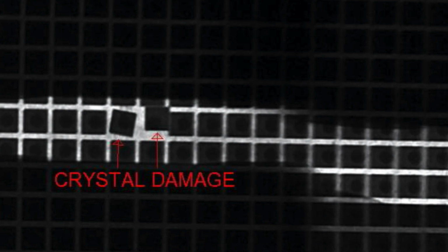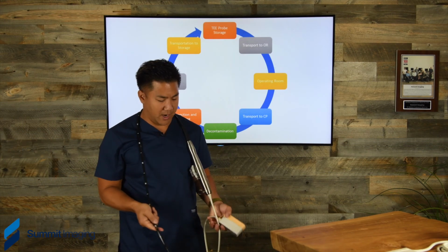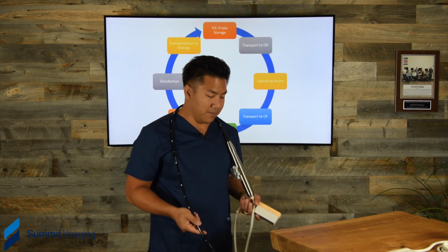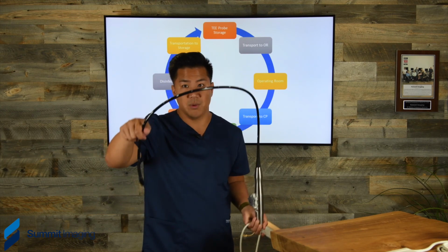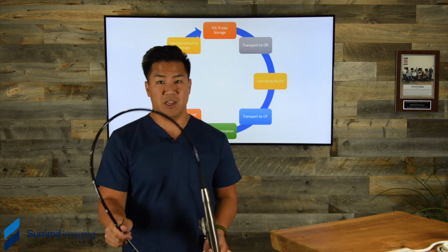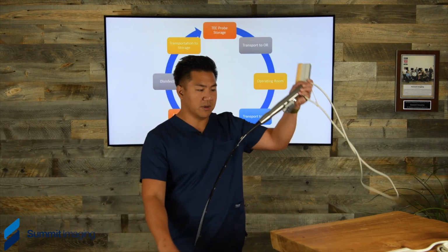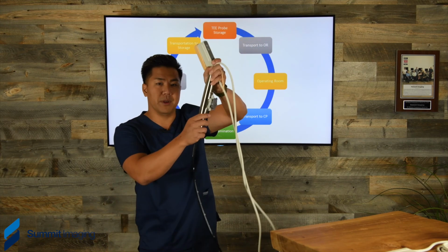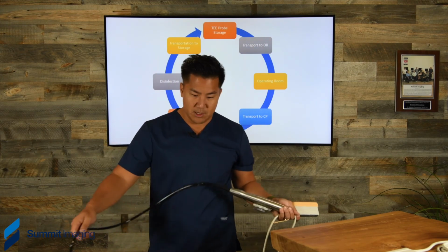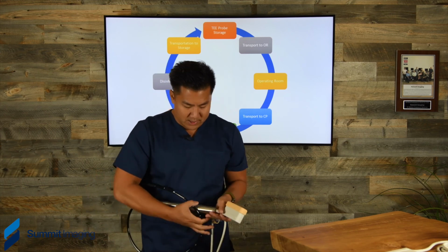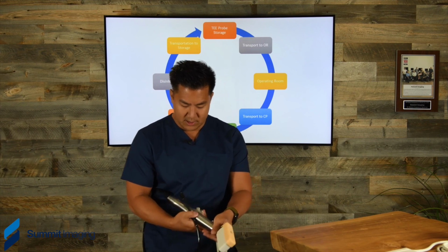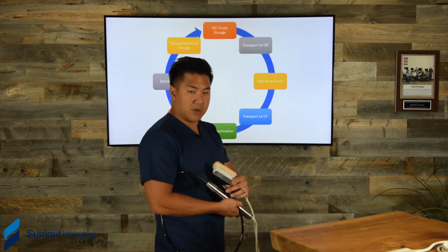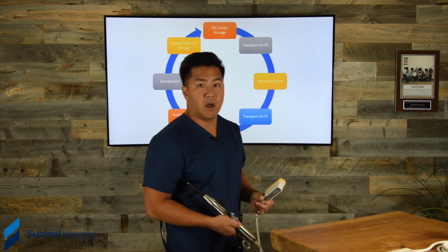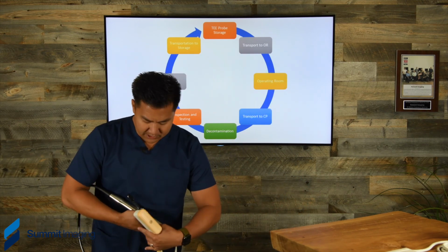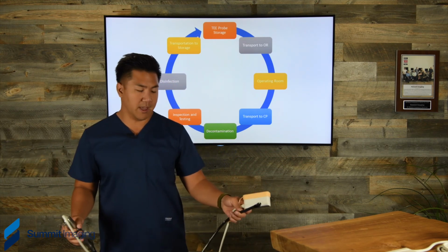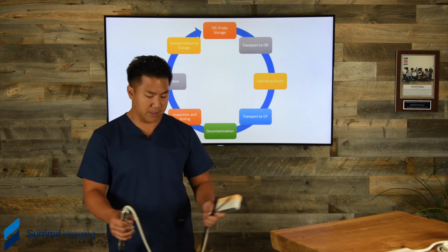And so what we've seen is everything from hospital employees trying to carry it like this, which we don't recommend, because you don't want this touching you, especially after it just came out of surgery, or if it just got used on a patient. You really don't want this entire insertion tube touching you at that point without the proper protective gear. We've seen people roll them up with the tip right here, and as they're walking around, the tip starts banging, as you can hear right now, on this metal casing here. We've even seen customers walking like this, and then the tip bangs on the can of the transducer.